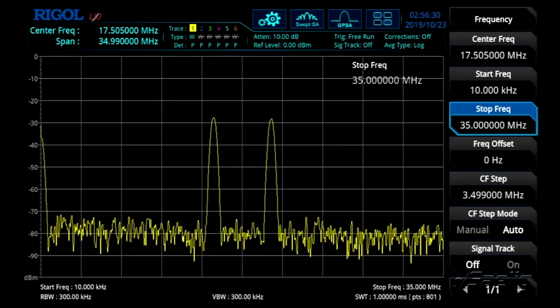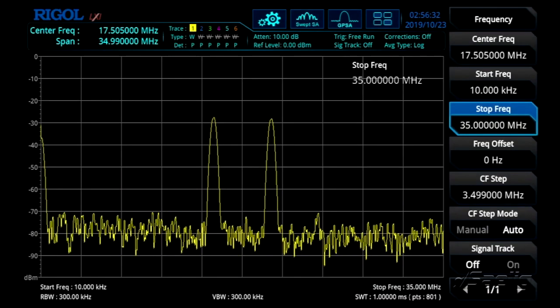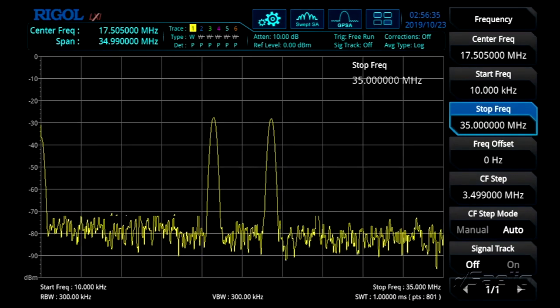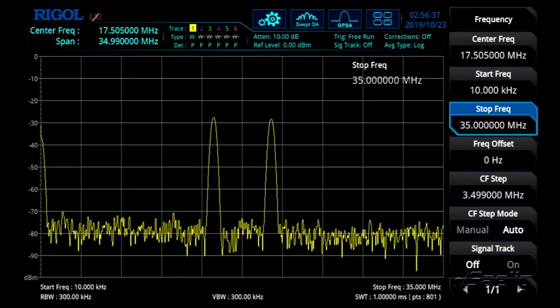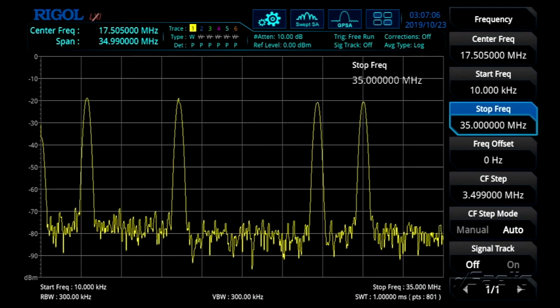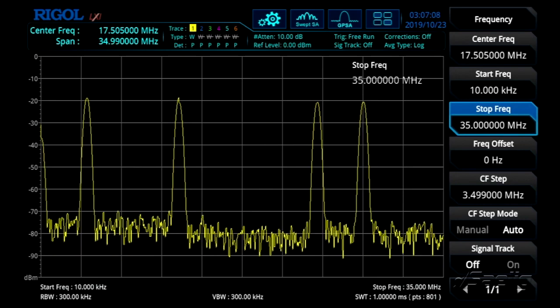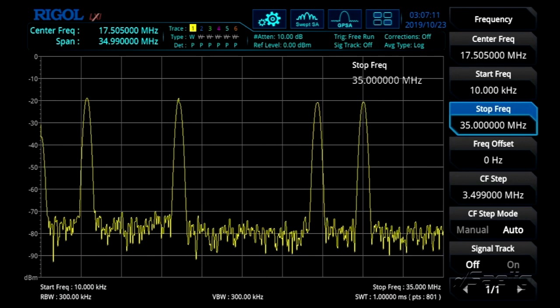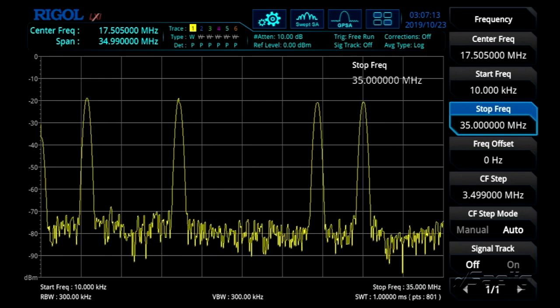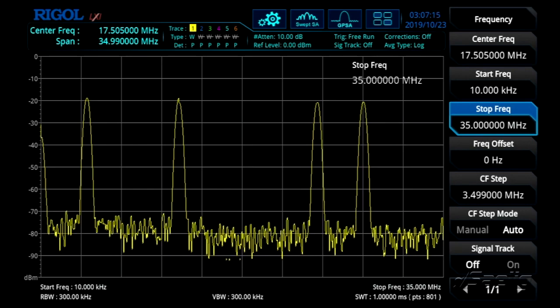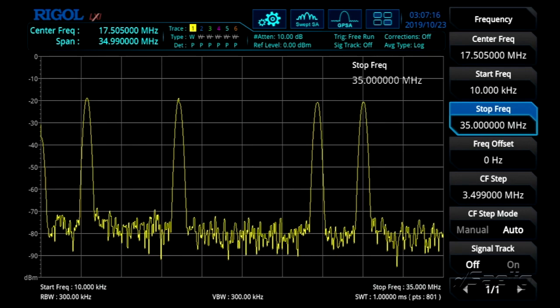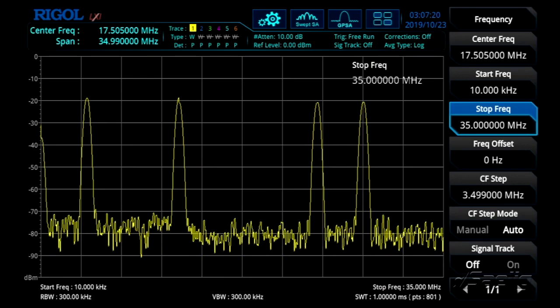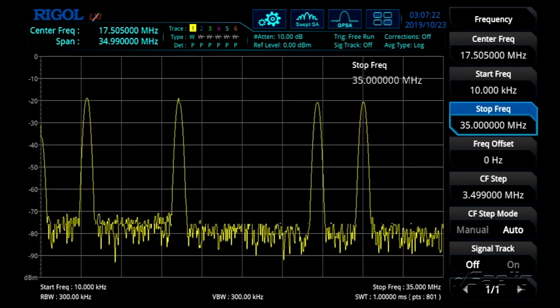The dual tone function allows the user to create a function that has two sine waves multiplied together, allowing you to independently control each sine wave's frequency. The harmonic function allows a user to define which harmonic — up to the eighth harmonic — they would like to have created and that harmonic's particular power level. Both dual tone and advanced harmonic generation are great for testing different types of filters.